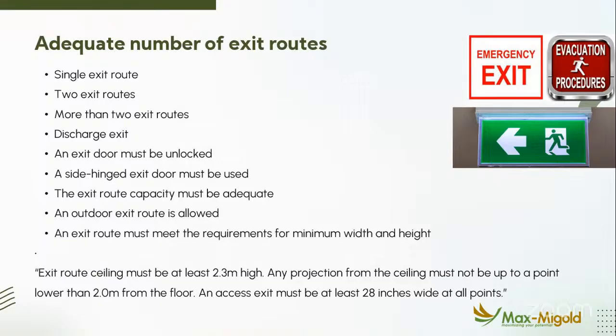Depending on the size or complexity of the building, meaning how many stories it has, how many people stay there, and so on, we recommend different widths and heights for the emergency exit area. We said the emergency route must be at least 2.3 meters, and could be more depending on the complexity.